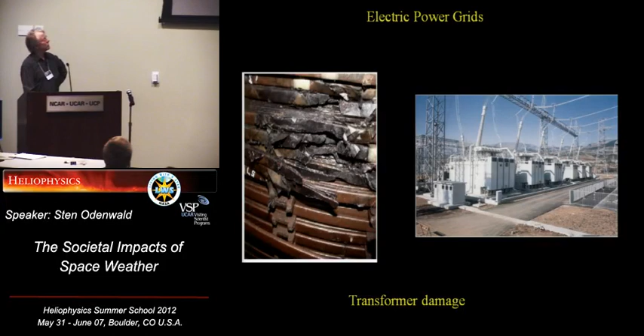Modeling this is actually fascinating. John Kappenman has worked on the 1989 storm and the 1921 storm. The 1989 blackout storm can be modeled very accurately these days in terms of the electrojet and the ground currents. When you put in an actual model of what the power grid looks like in terms of the transformers, couplers, capacitors, and whatever else, you can actually make predictions about how much GIC you should see at each node within a grid. That's the new generation of modeling the electric power grid in the face of GICs produced by geomagnetic events.